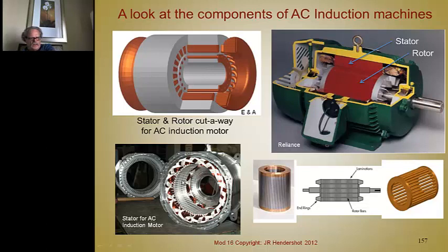And here's a machine where the core is put inside. You see all the coils and the end taping and lacing in the end turns. There's the lamination core without the coils in it. Here you see a cutaway provided by a machine tool spindle company in Switzerland called E+A. And this shows the copper bars, the copper end rings. This is a small one, so they silver solder these bars to that ring. They use round bars, and they silver solder that. And here's your windings and end turns for the stator.